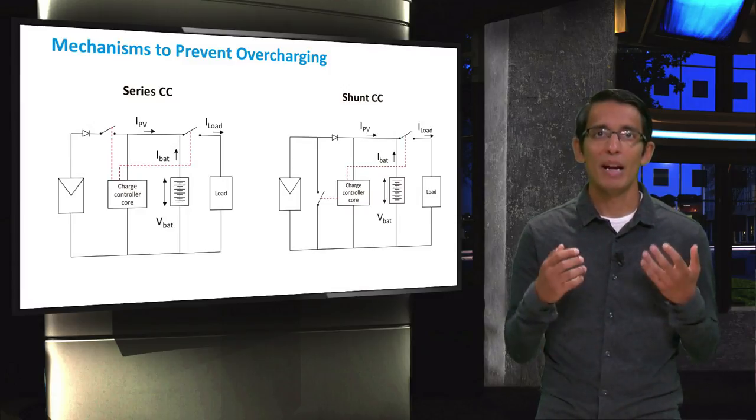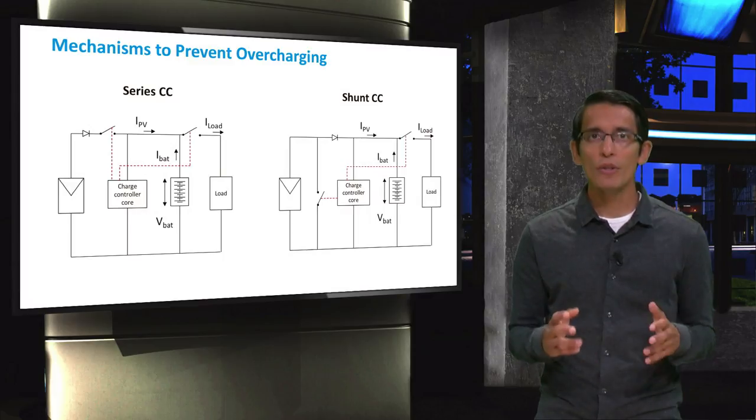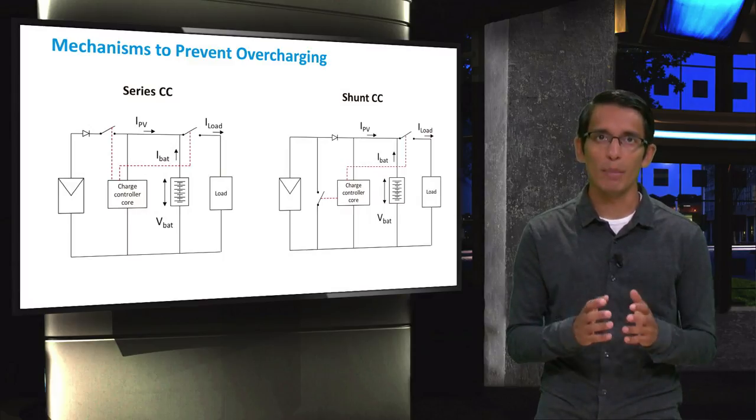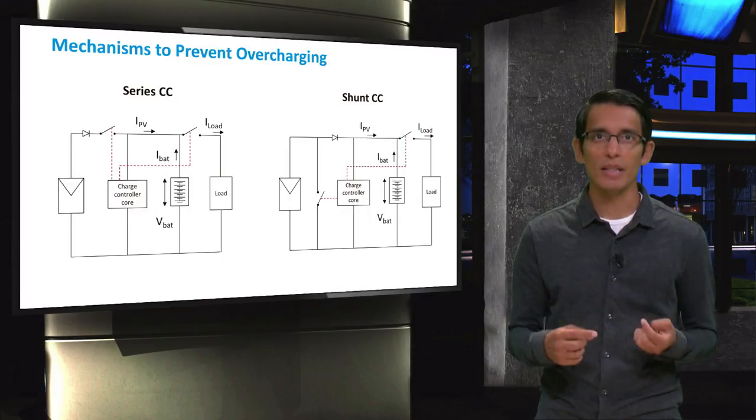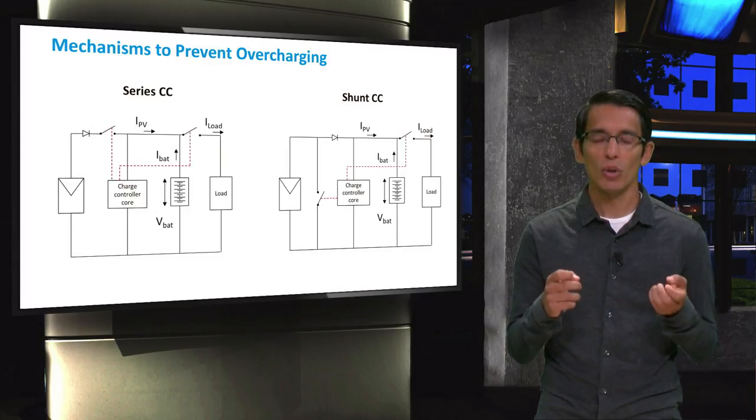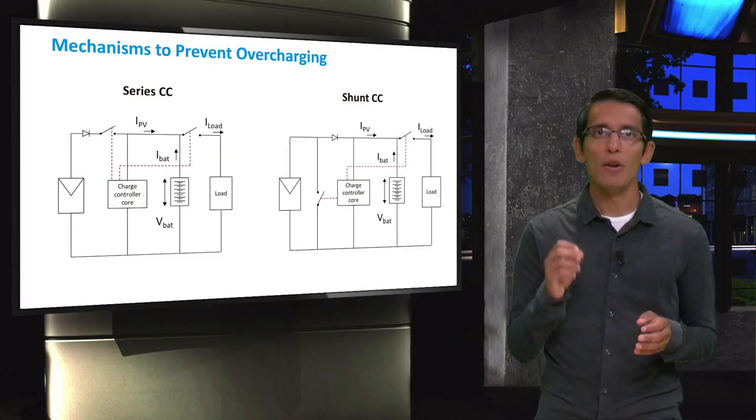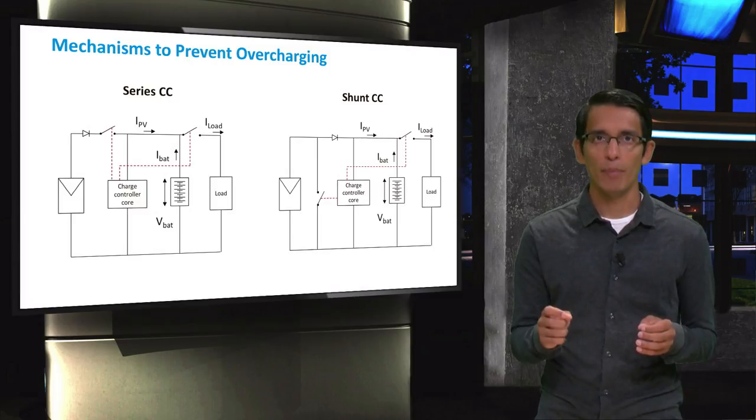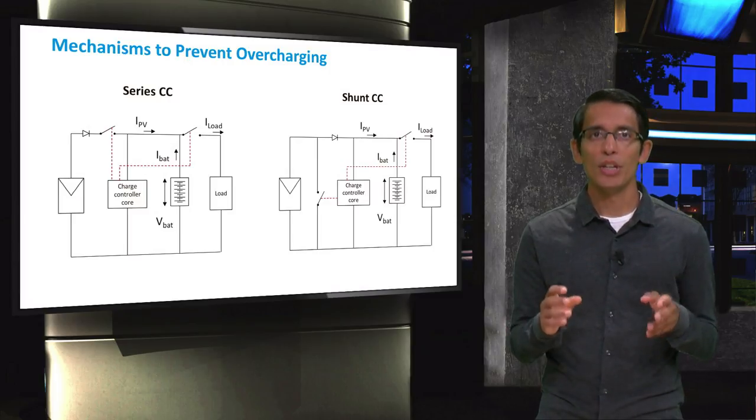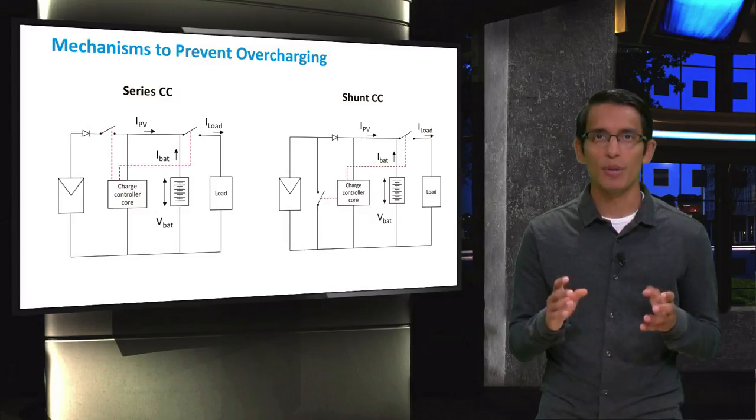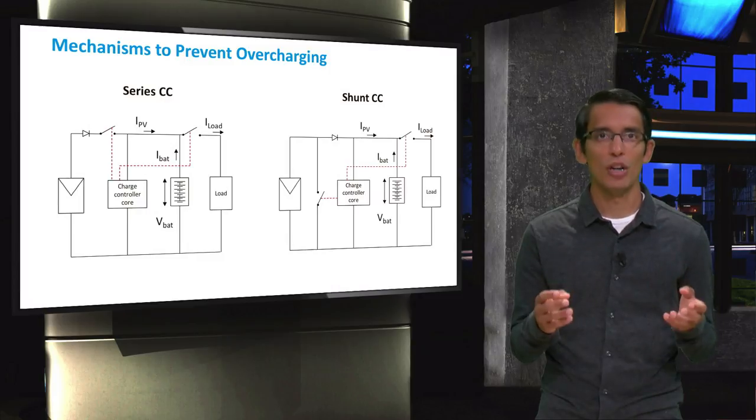On the other hand, in a parallel or shunt controller, overcharging is prevented by short-circuiting the PV array. This means that the PV modules will work in short-circuit mode and that no current will flow into the battery. Both of these topologies also ensure over-discharge protection. This is achieved by power switches for the load connections, which are appropriately controlled by the charge controller algorithms.